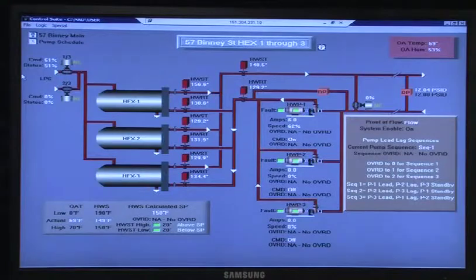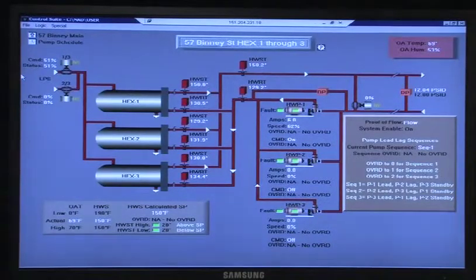Hold on a minute. Oh, I see. I'm trying to figure, so high, you're putting at the low. It's at 70 degrees outside. You're going to be at 150 degrees Fahrenheit. And then you're sitting in the middle is what it's actually doing. It's 69 degrees out, and we're at 150. So it's actually scalable and it's working right. And at 130 degrees you go into a low alarm. To calculate the math, the high above and belows will be based on that actual.